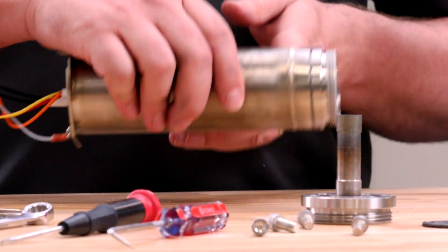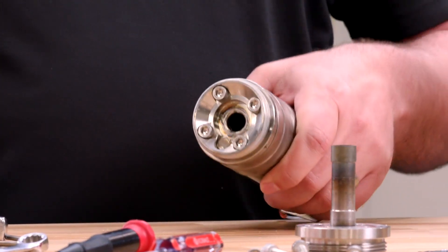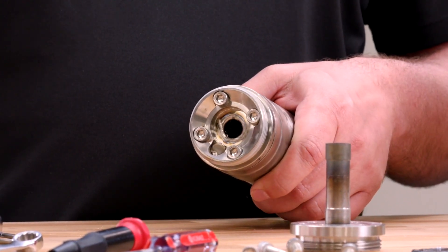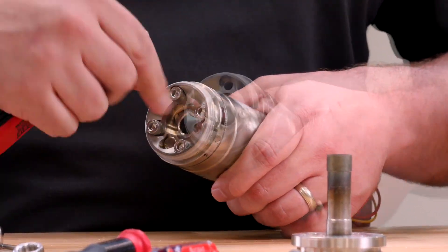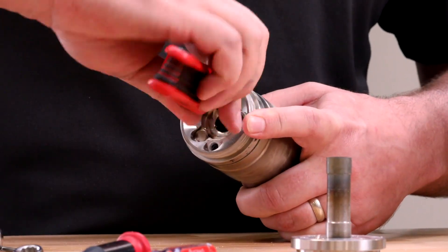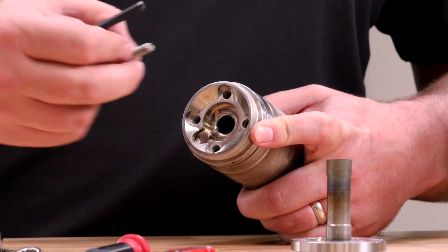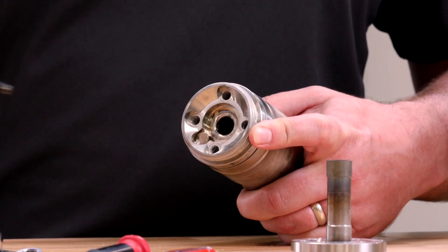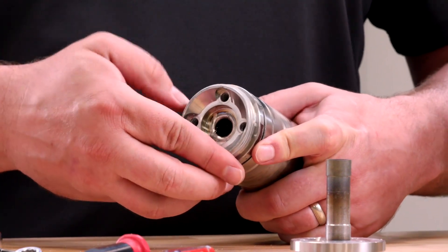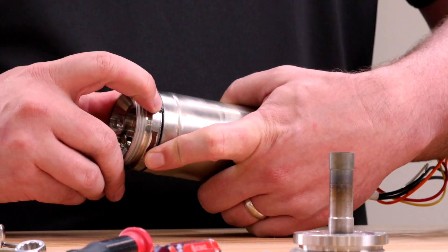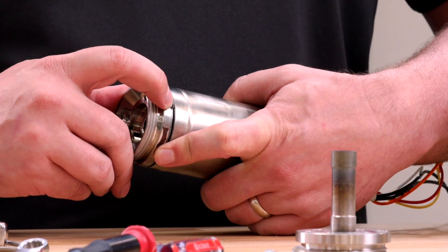Now that the assembly is free from the sensor housing, remove the four cap head screws from the O2 cell with a 5mm Allen wrench. The O2 cell can now be carefully removed from the heater tube. The cell flange has a notch that may be used to gently pry the flange away from the heater tube.